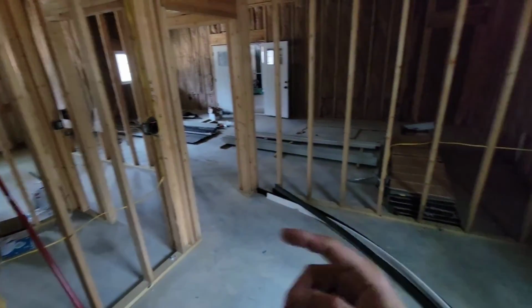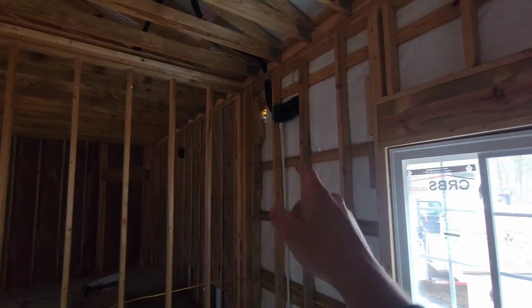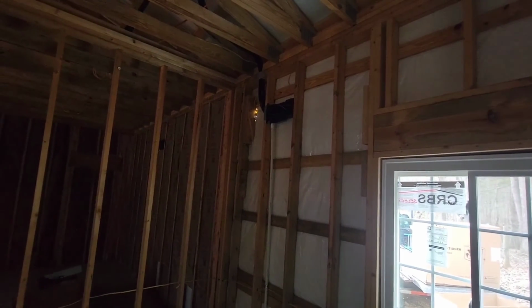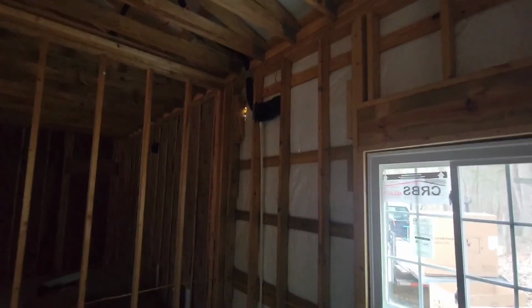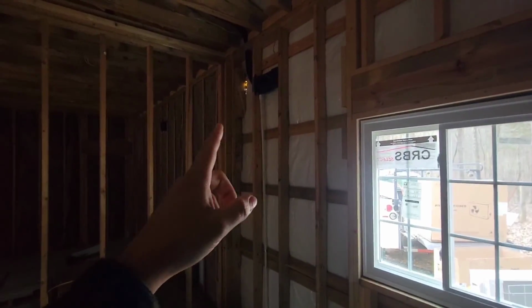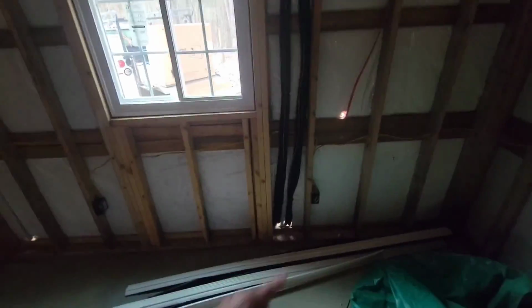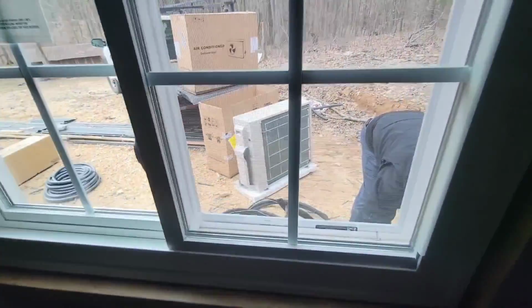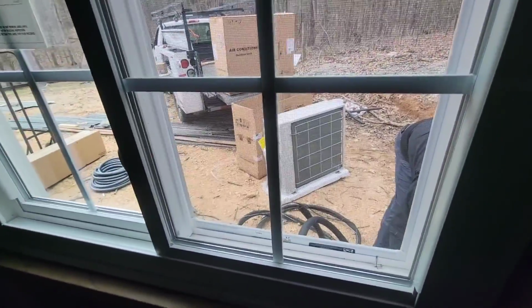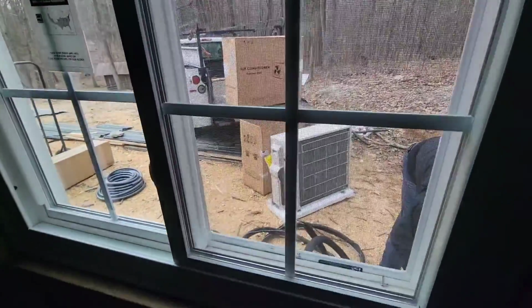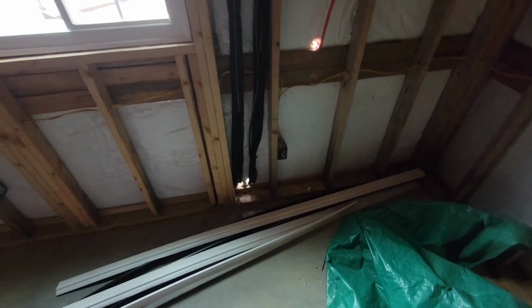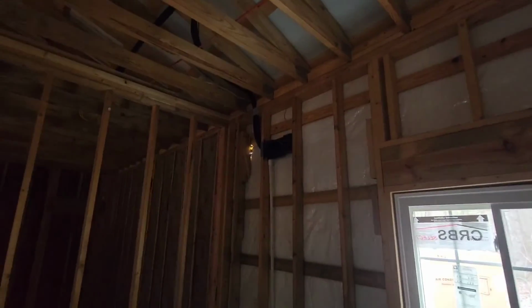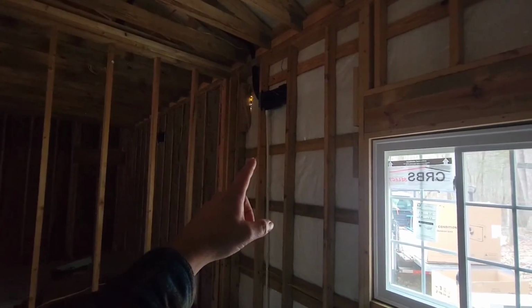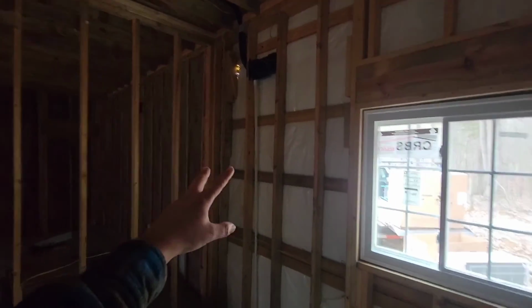Since this room is not more than 250 square foot, I didn't want to do a 12K or anything over a 12K. Plus, you got to make sure that you don't exceed the capacity of the outdoor unit. You can see we're about to set that outdoor unit there. We got both outdoor units, so we're about to finish this job. It's going to be nice. I was able to shave about $2,000-$3,000 off the price by just doing 2 heads in that 2-ton outdoor unit.